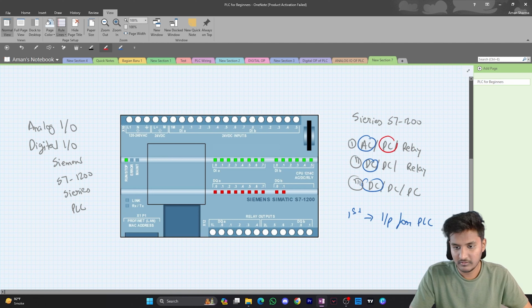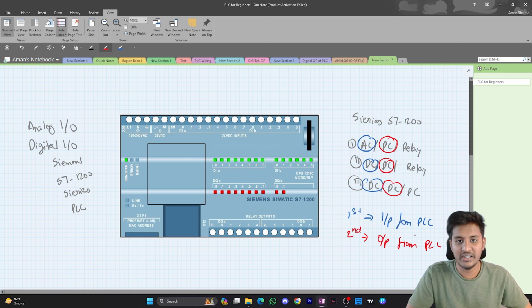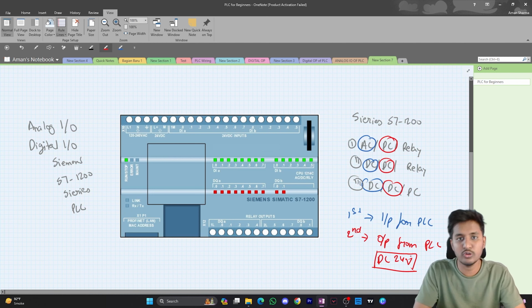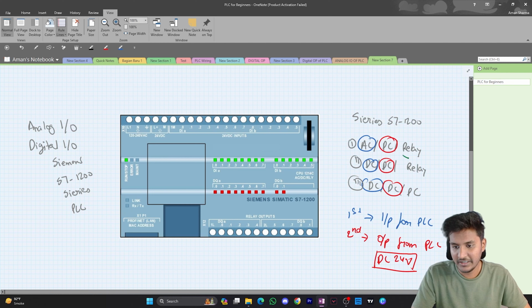The second one is the output from the PLC. This series will only give a DC output, generally DC 24 volt, and this output we use to make our PLC a sinking or sourcing type PLC. The third one is the output here meaning the signal output, or you can say output signals.